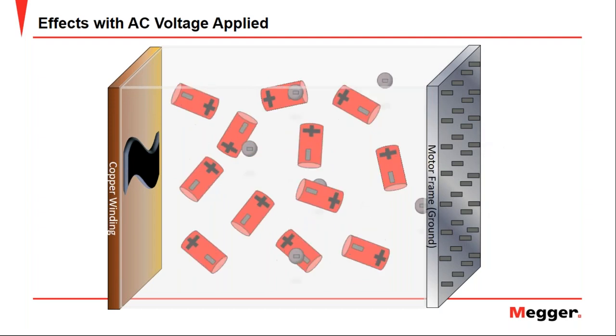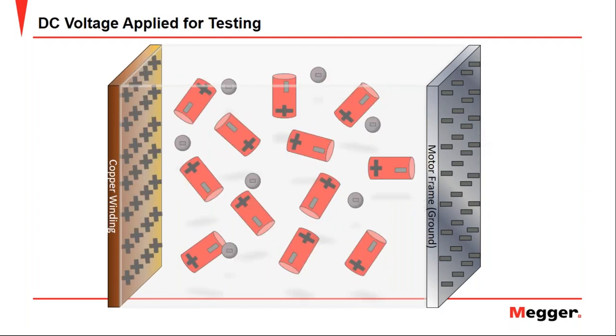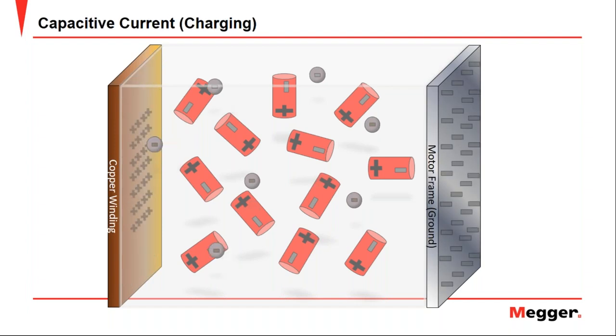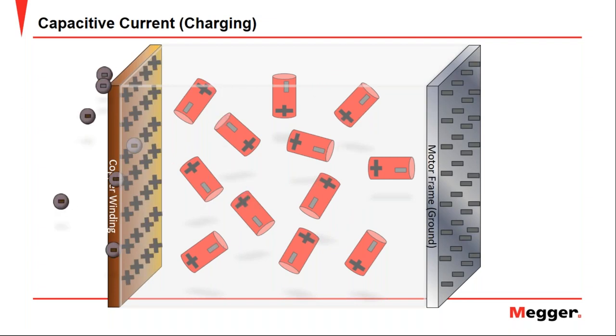Now, let's apply a DC voltage and see how it affects the electrical circuit. When we supply the motor with the DC voltage, the behavior is completely different, and we can see how immediately after applying the voltage, the first thing that happens is that the free electrons present in the insulation now move quickly towards our positive pole, in this case, the winding.